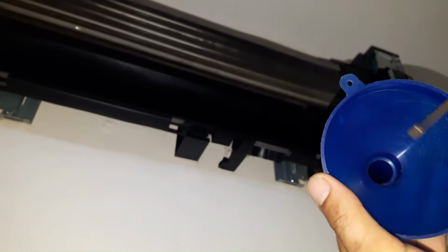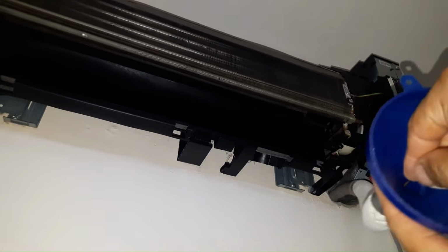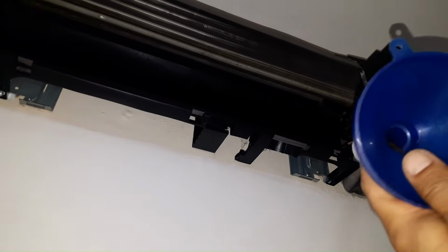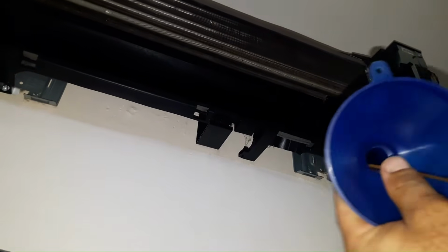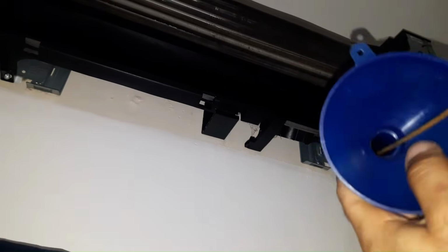I got this fish tape. If you don't have one, you can use a wire inside the water line to clean the mold. Your AC drain line can become clogged with mold and mildew that forms in standing water within the drip pan. Or, an AC drain line clog could be caused by general dust, dirt, dander, or debris accidentally entering the drain line.